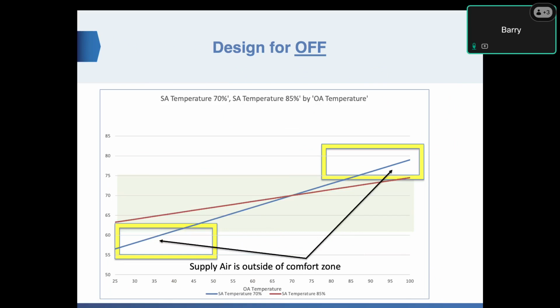And the reason we call it design for off is the box here, this light shaded box, is the comfort zone from about 62 degrees to 75 degrees. If you're bringing air in that zone, then generally it's pretty comfortable. You're not going to be feeling cold drafts. You're not going to be feeling warm air, and it'll mix and distribute into the space very readily. And the heating cooling system can easily then manage it. If you're outside of that zone, in the heating season here, at 70%, you fall outside of that zone at about 43 degrees.